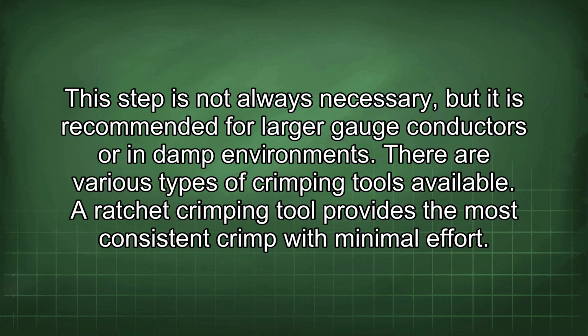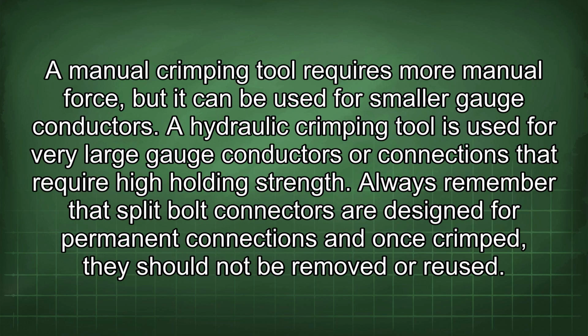There are various types of crimping tools available. A ratchet crimping tool provides the most consistent crimp with minimal effort. A manual crimping tool requires more manual force, but it can be used for smaller gauge conductors. A hydraulic crimping tool is used for very large gauge conductors or connections that require high holding strength.